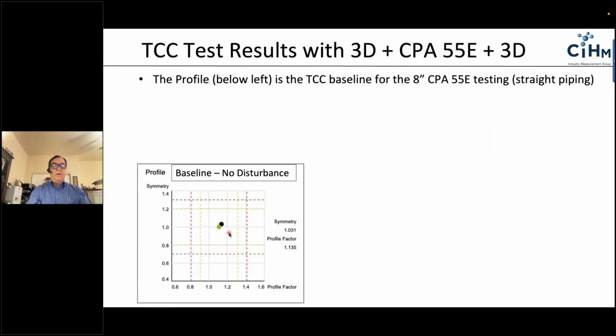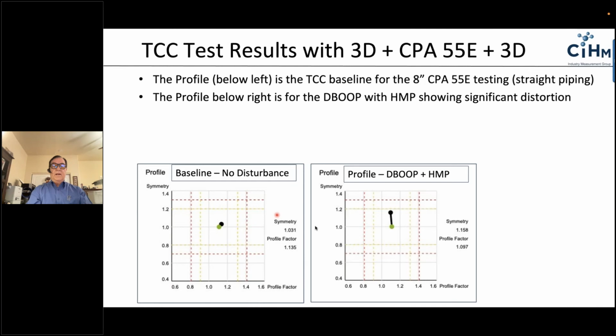Now baseline means 100D of straight pipe, with the CPA 55E installed at 3D upstream of the meter. Here is the double elbows out of plane with a half moon plate. We can see a very substantial shift. Now these graphs all have the same vertical and horizontal axes for this meter test, as well as the ones I show you for the 6-inch meter. So we can see the symmetry here is about a 1.15. This is about a 13% deviation, or 12%, from the baseline testing. Both these graphs were taken at about 7 meters per second. This was at baseline at the lab, and this is baseline with the double elbow out of plane.